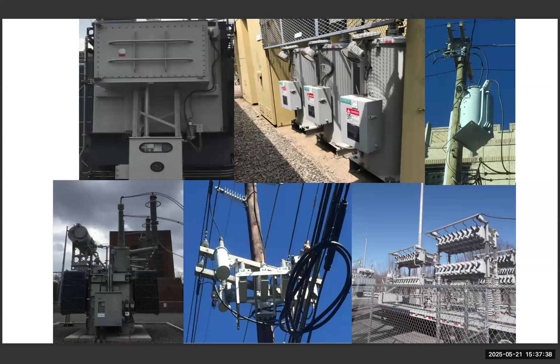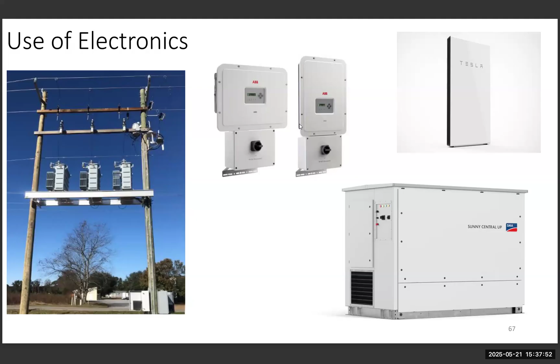So again, how do you regulate the voltage? You have the transformer tap changer, voltage regulator, capacitor banks, shunt reactors. However, now you can see in the picture we have StatCom, a device on the left that moves like 30 times per second. You've got small inverter, large inverter, energy storage, large one behind the meter. The point I'm showing you is that the system has changed significantly.